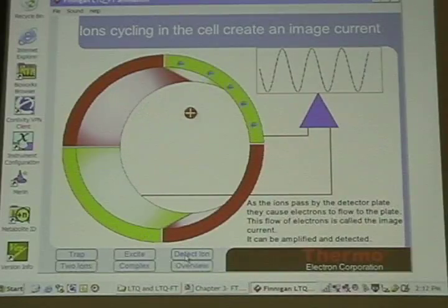So let's say you have a very complex mixture elute, but you want extremely high mass accuracy for one of those guys. You SIM him. You do a data-dependent remeasurement of just him without all the other crap. You get very high mass accuracy. This is how Matthias Mann will do the first scan at 4 or 5 million ions. And then he'll remeasure one of those by itself at a good ion population, 200,000 ions, and he gets extremely high mass accuracy. He'll go from measurements of 5 or 6 ppm down to 0.1 or 0.2 ppm. Okay, does that make sense? Cool. Any questions about this process?